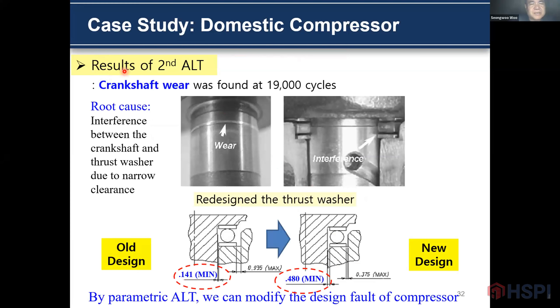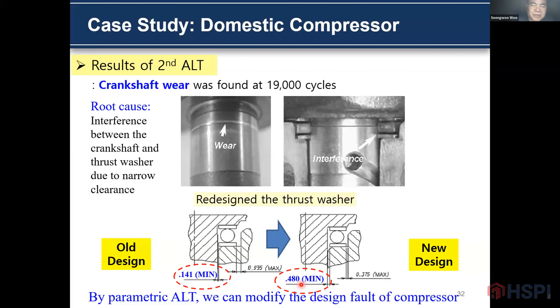This is the result of the second parametric ALT. A crankshaft failure was found at 19,000 cycles. It came from interference between the crankshaft and the thrust washer due to narrow set clearance. This is the old design and this is the new design. We modified the clearance from 0.1 to between 0.4 and 0.5. By parametric ALT, we can modify the design parts of the compressor.